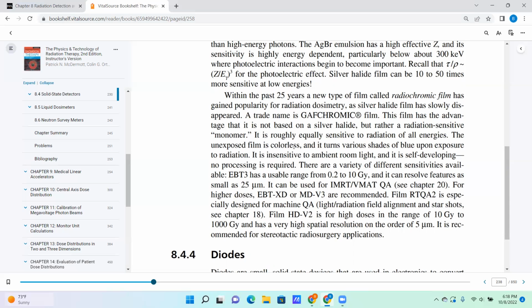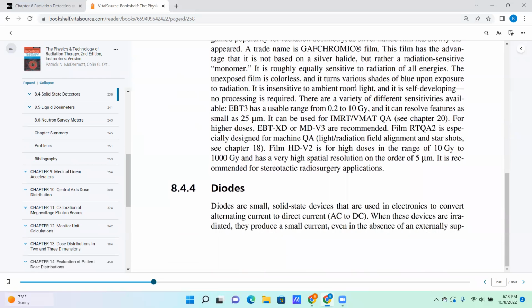The unexposed film is colorless and it turns various shades of blue upon exposure to radiation. It is insensitive to ambient room light and is self-developing. No processing is required. There are a variety of different sensitivities available. EBT3 has a useful range of 0.2 to 10 gray. It can resolve features as small as 25 micrometers.